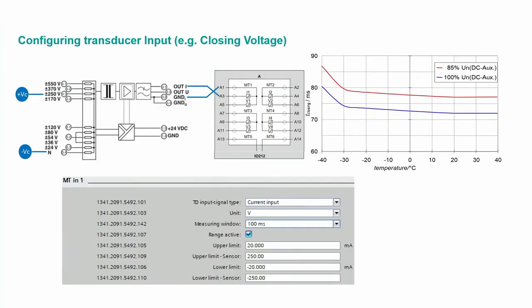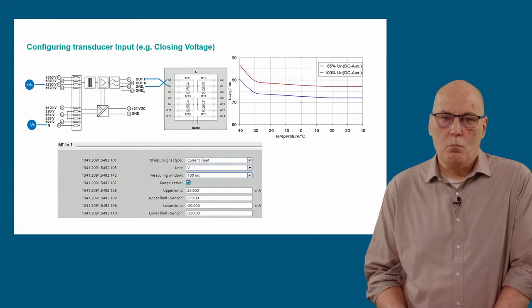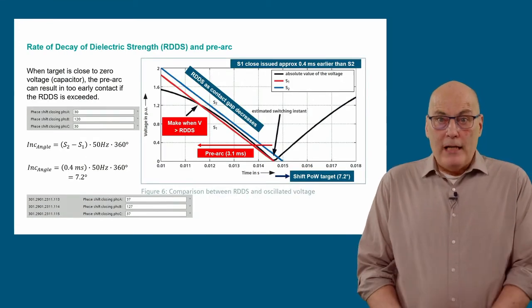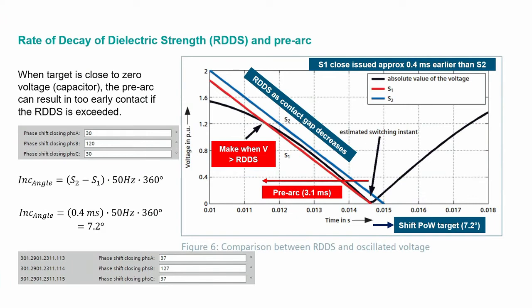The transducer inputs for compensation are configured in the normal manner. Set the scaling parameters according to the transducer rating and be sure to select current or voltage as the input signal depending on the nature of the transducer signal. A final aspect before Chapter 3 is the rate of decay of dielectric strength, simply called RDDS. This can be of importance for some applications, especially for capacitor load closing.